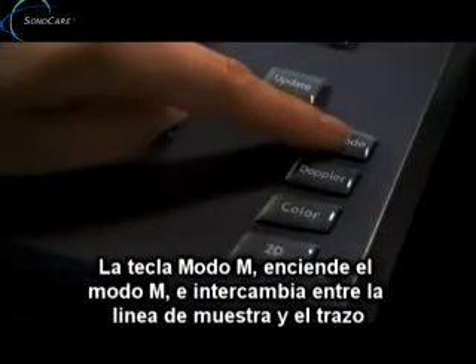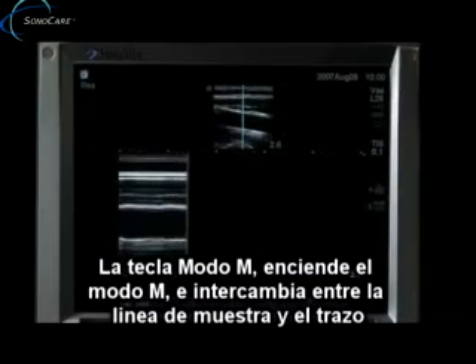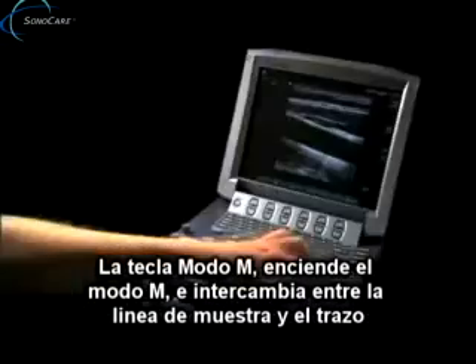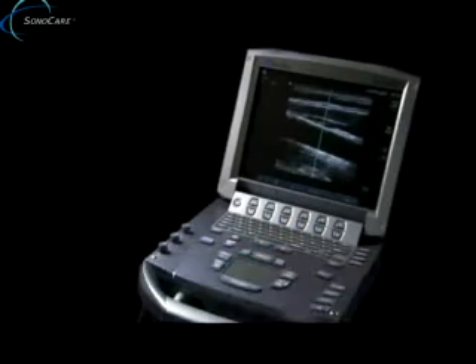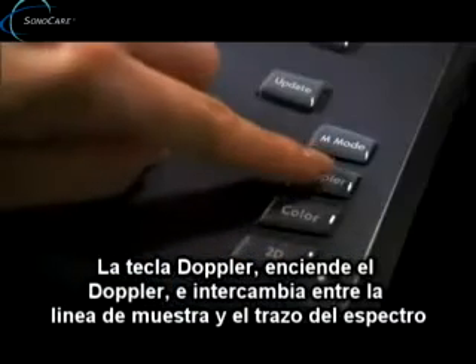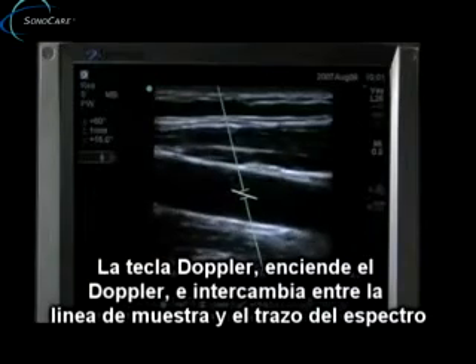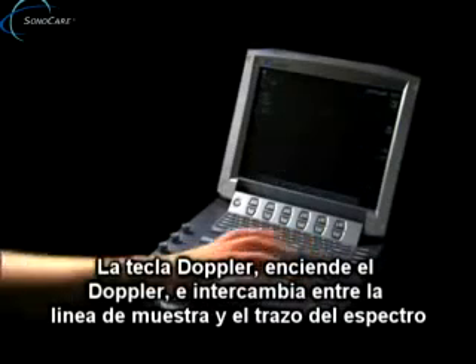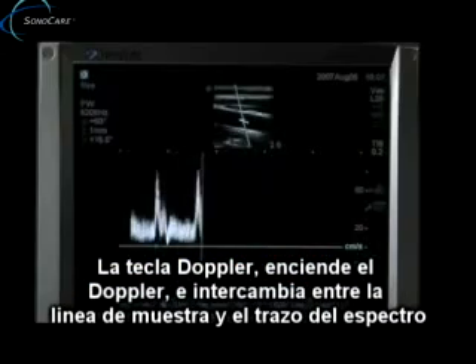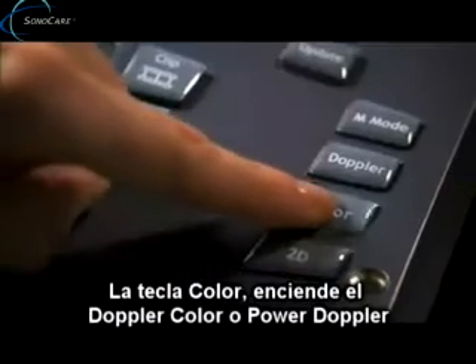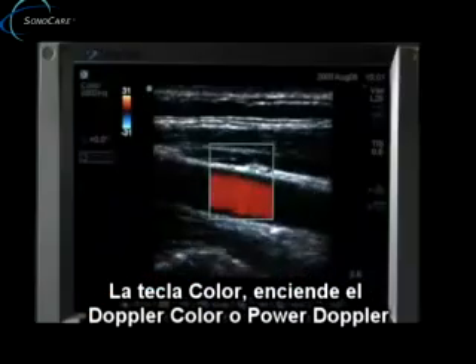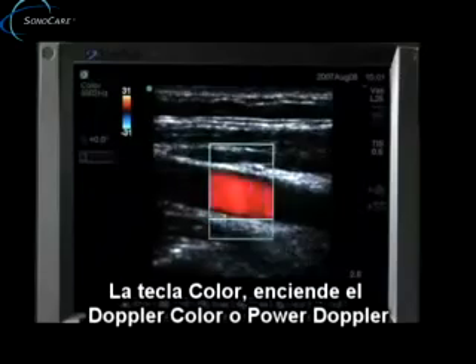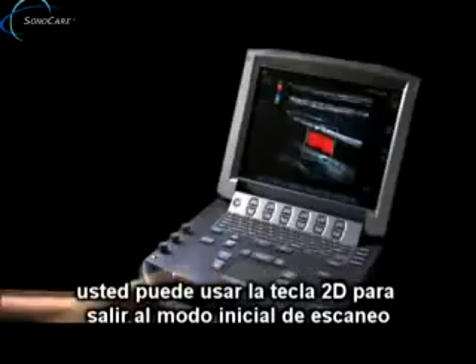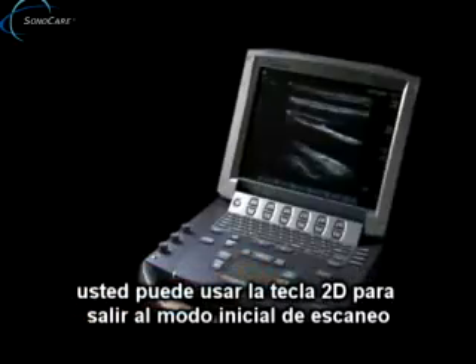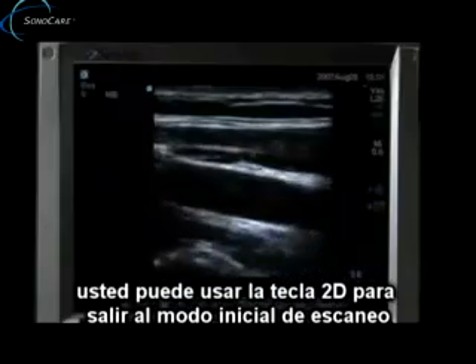M mode turns M mode on and toggles between M mode sample line and M mode trace. Doppler turns Doppler on and toggles between Doppler sample line and Doppler trace. Color turns Color Doppler or Color Power Doppler on and off. You may use the 2D button to exit any scanning mode and return to 2D imaging.